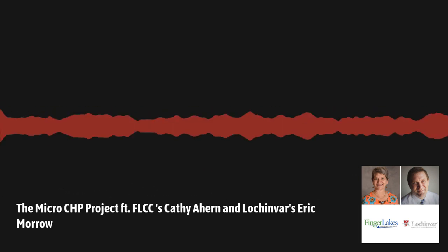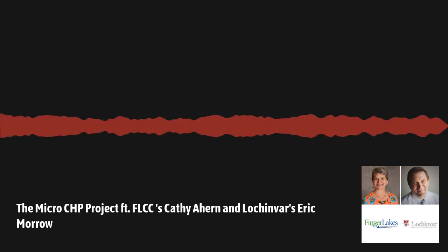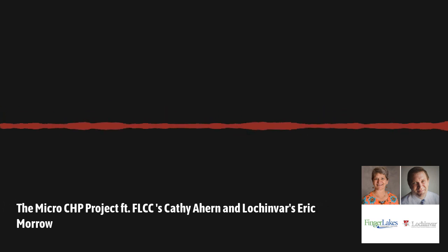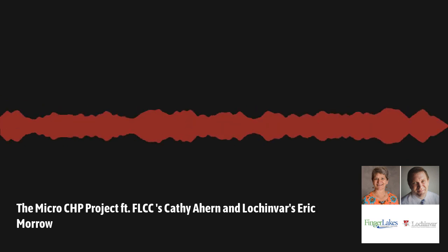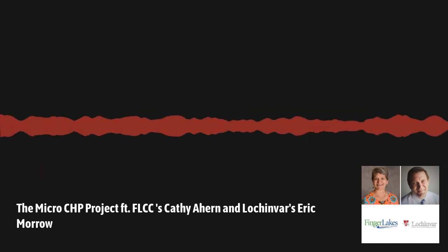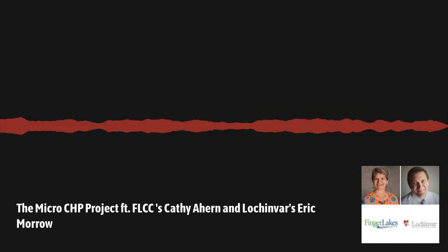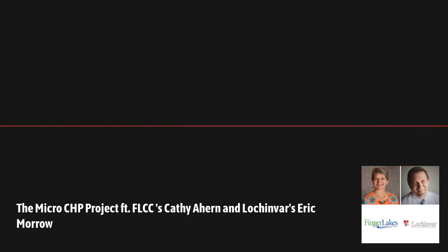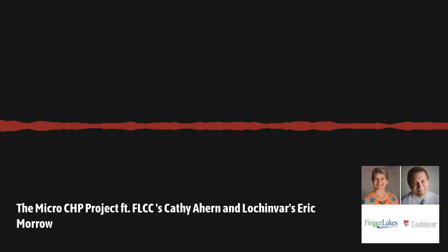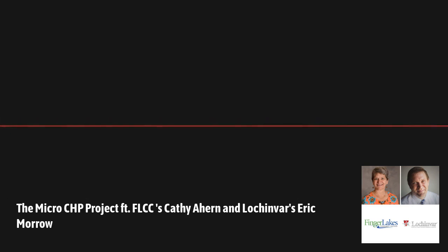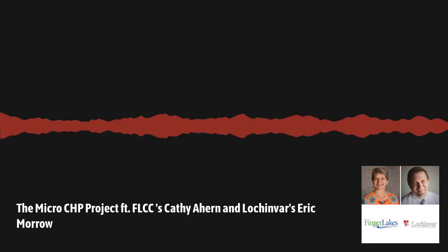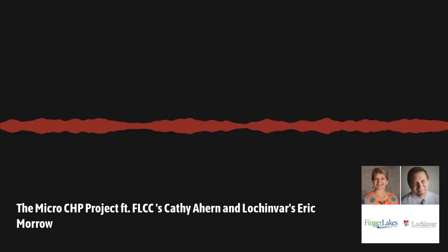In most systems, I always tell somebody: if you have over 1 million BTUs of heating capacity designed into your system, you might want to look at putting a micro CHP with it, because there's enough load to keep it running all the time or most of the day. And you can then put less use or stress on your other heating appliance.